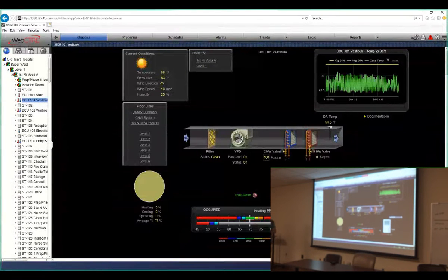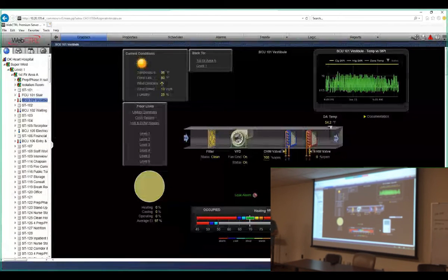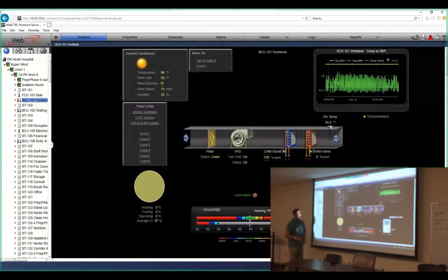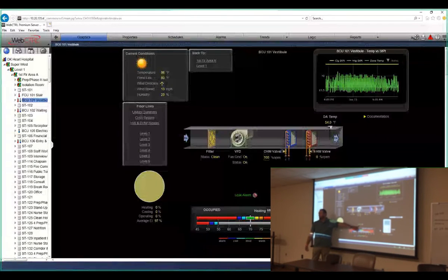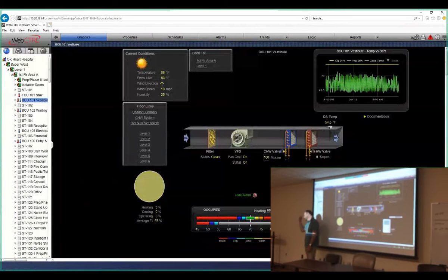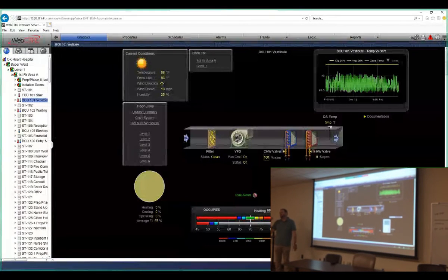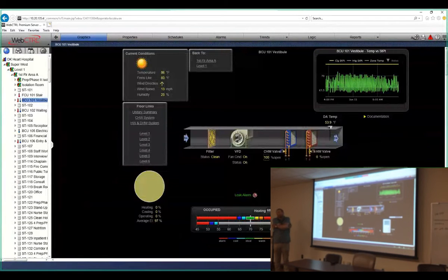All these blower coil units have a leak alarm. One thing that's kind of different is each one of these blower coil units has a leak alarm. We're monitoring: if the condensate pan overflows, we have a switch inside the unit that will trigger and tell us if that condensate is overflowing, and it will shut the chill water valve off. It's not going to shut the fan off.